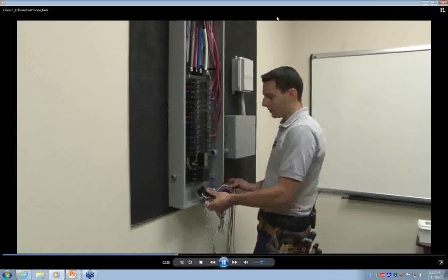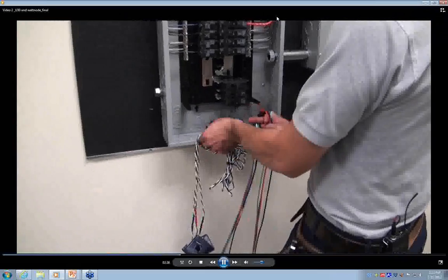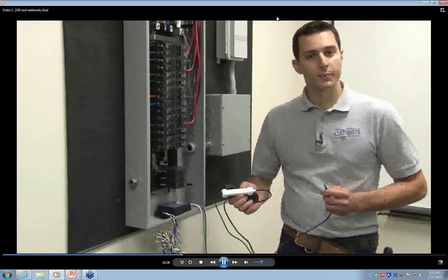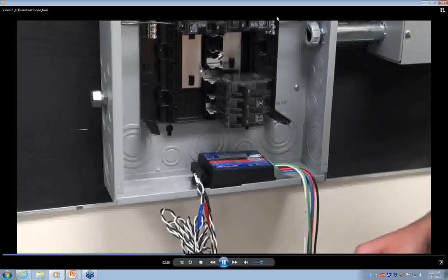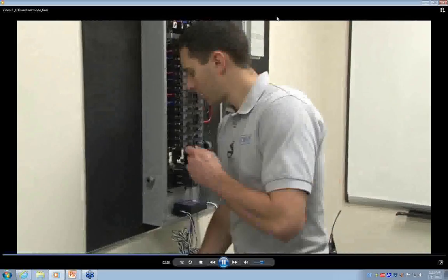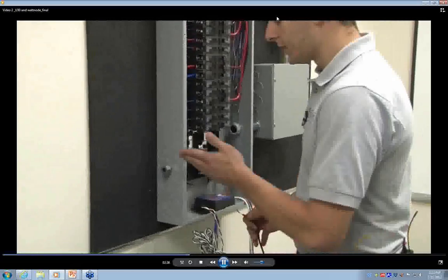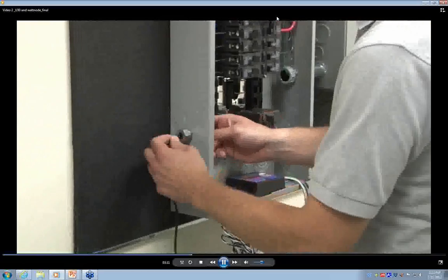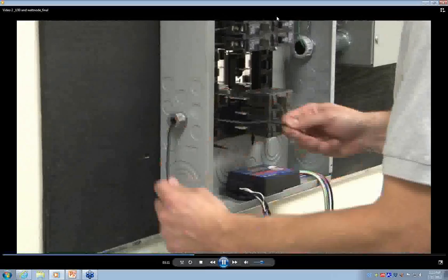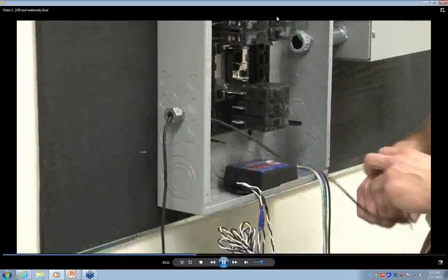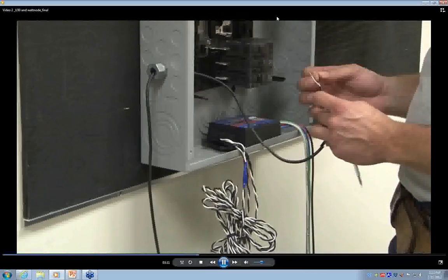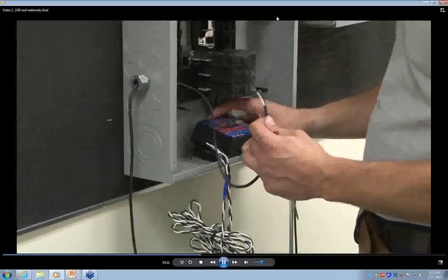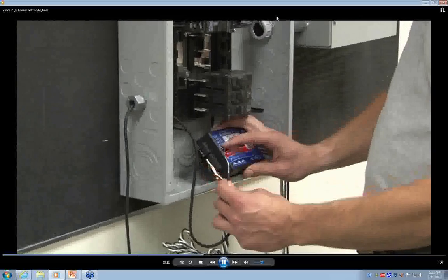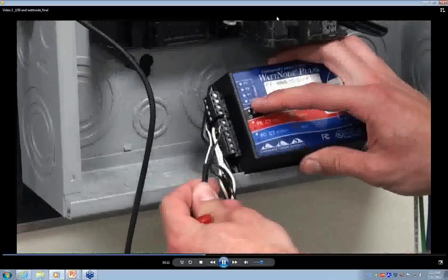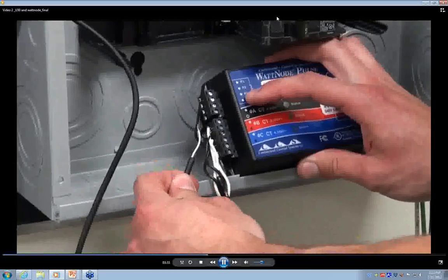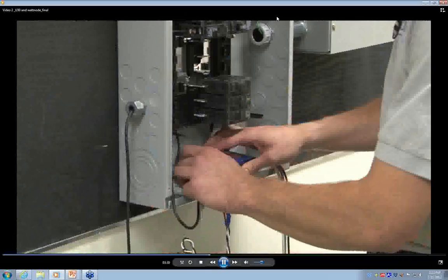We'll place the watt node in the location where we've determined. We can now run the Onset pulse input adapter cable to our watt node. We'll do so using the listed fitting to bring our cable into the panel board, and we'll wire it directly to the watt node. This cable has a black and white conductor. The black will be connected to the common, and the white wire will be connected to P1. Normally we will not use P2 and P3.